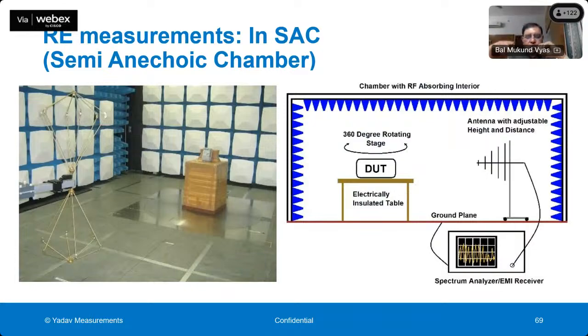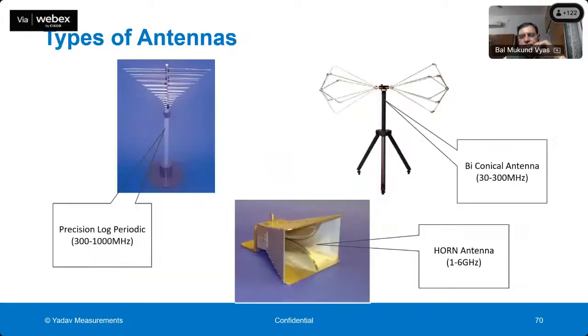And there are limits specified in the CISPR standard and the energy meter standards as per BIS and IEC standards. So various kinds of antenna are used for different frequencies. You can see the precision log periodic antenna is used for 300 megahertz to 1000 megahertz, the biconical antenna is used from 30 megahertz to 300 megahertz, and the horn antenna is used from 1 gigahertz to 6 gigahertz.